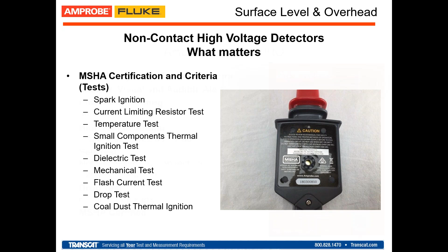So Fluke has one under the brand Amprobe. It's called the TIC 300 Pro. As I mentioned before, it is a high voltage non-contact detector, and the range goes from 300 volts all the way to 1500 volts AC for the low range setting, and it has a high range setting that goes from 1500 volts AC all the way to 122 kV. There are other brands in the market that go all the way to 200 kV.